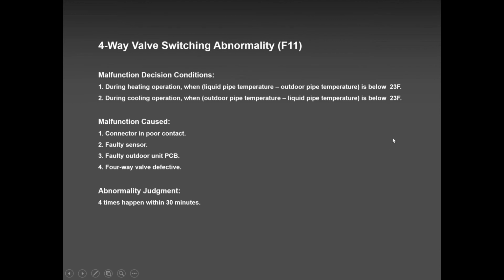And guess what? Oh, Paul, you told me to change the four-way valve, and I have the same problem. And when the unit comes to me, I cut and open, and this is what I see. The inside got melted. A brand new four-way valve coil. They did not put the wet cloth, and now it got overheated, and that's the problem. And I'm not making up stories, guys. I'm telling you fresh from the field, and I've seen it.